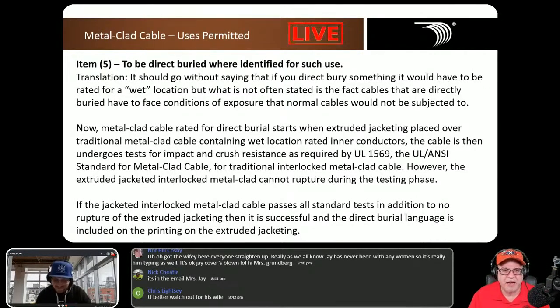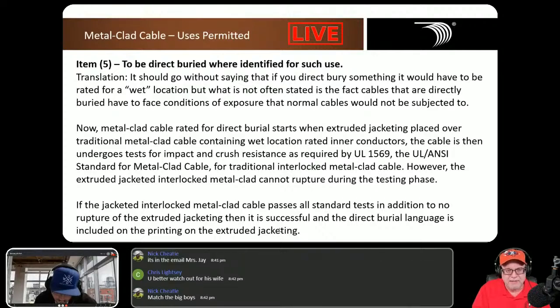Nothing, we're it, baby. All right, let's look at this real quick. Item number 5, direct burial where identified for such use. This is where we first start to see something where we can take MC cable and directly bury it in the earth. We're also starting to see some of the things that set the stage for being able to put it, for example, in concrete. Let's look at this.